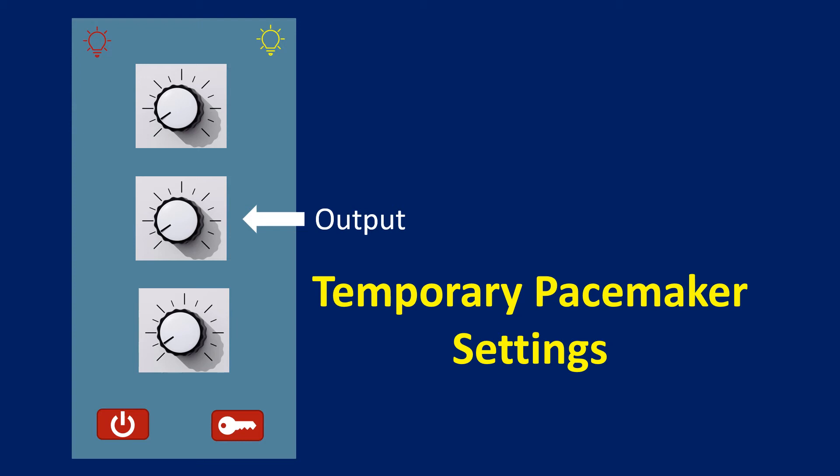Pacing output setting is decided after testing the pacing threshold. Threshold is checked by gradually reducing the output until pacing capture is lost, and then quickly raising it back. Usually, output is set at 3 times the threshold for temporary pacemakers. Higher safety margins may be used if the patient is restless and likely to have lead displacements. Threshold should be checked at least once daily to ensure a good safety margin.